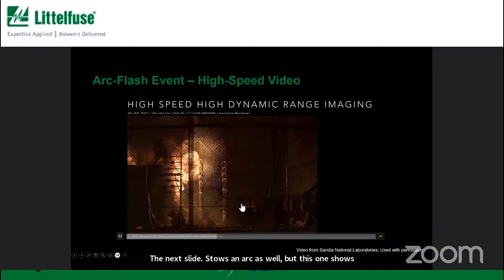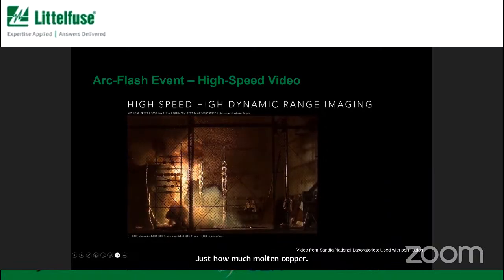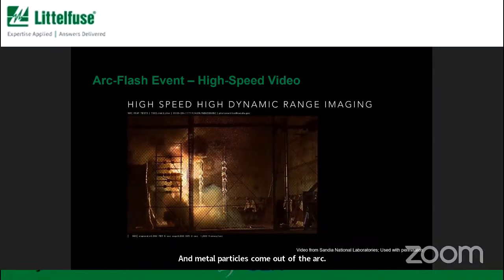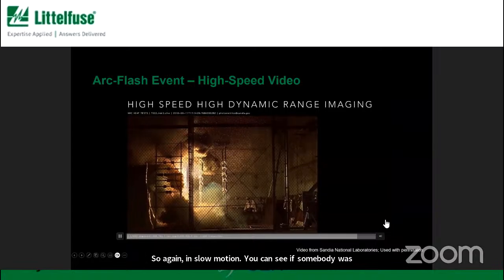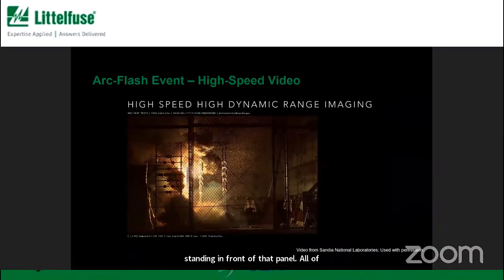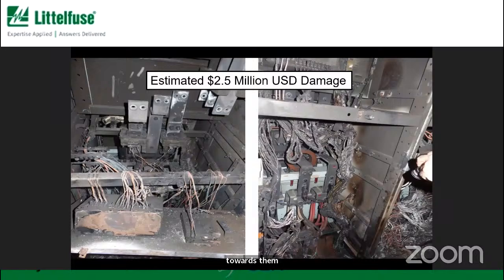The next slide shows an arc as well, but this one shows just how much molten copper and metal particles come out of the arc. So again, in slow motion, you can see if somebody was standing in front of that panel, all of those red hot liquid metal particles would be coming out towards them. So, of course, there's a risk to people standing nearby, but the equipment itself can also be completely destroyed. And the building can end up with a fire. Replacement equipment could take many weeks or even months to get, and it is very costly in terms of damage.